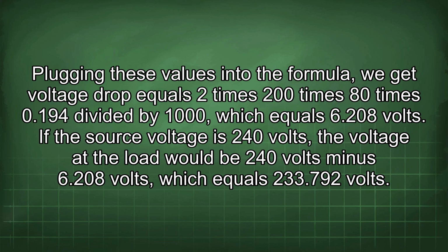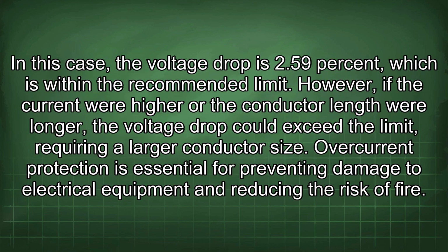If the source voltage is 240 volts, the voltage at the load would be 240 volts minus 6.208 volts, which equals 233.792 volts. In this case, the voltage drop is 2.59%, which is within the recommended limit. However, if the current were higher or the conductor length were longer, the voltage drop could exceed the limit, requiring a larger conductor size. Overcurrent protection is essential for preventing damage to electrical equipment and reducing the risk of fire.